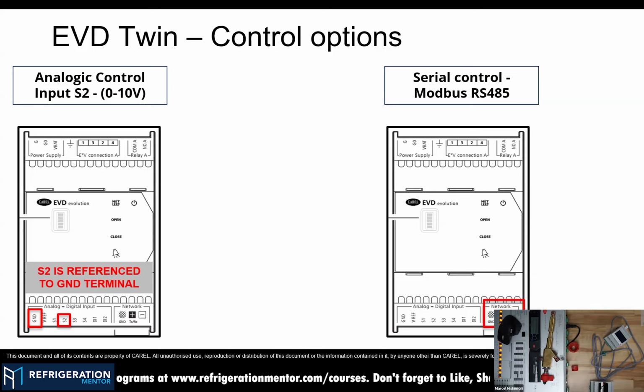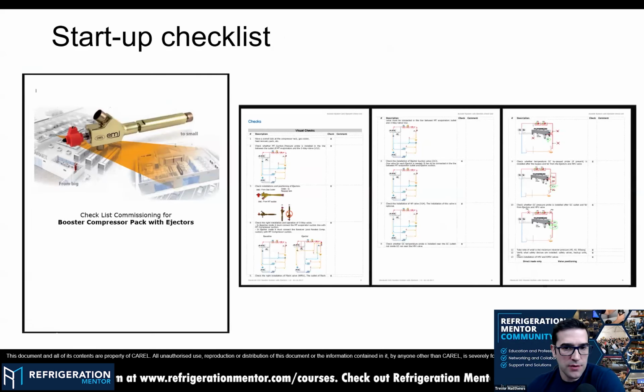The other way we can do it is with serial mode. Serial mode provides more feedback from the main controller and also from the supervisory system, because I can retrieve all the alarms coming from the driver and see them on the BMS. So you need to evaluate what you need, or normally the OEM evaluates whether they want easy troubleshooting with 0 to 10 volts, but susceptible to more noise, or serial mode where you can retrieve all the information. So two different ways of controlling the ejectors. Okay. Yeah, pretty straightforward. 0 to 10 or RS485 from our system.